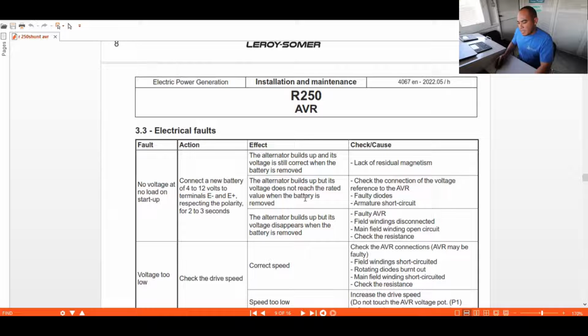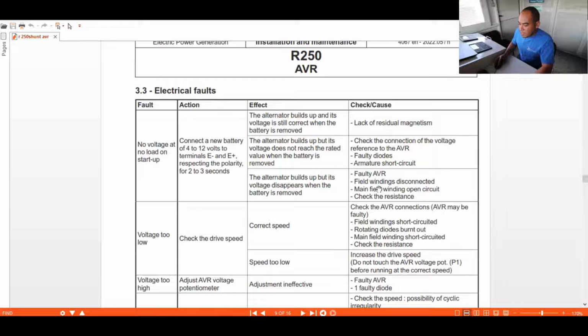Okay, for example, you excite it and it builds up, and once you connect your AVR back, or the connections are already fully connected, and still there is no voltage output. So you have to check the AVR connections, check the diodes if they are faulty, and check the armature for a short circuit. Here, the alternator builds up, but the voltage disappears when the battery is removed. Then either the AVR is faulty, or the main field winding is disconnected or open; check the resistance. So you have to check all of those things.